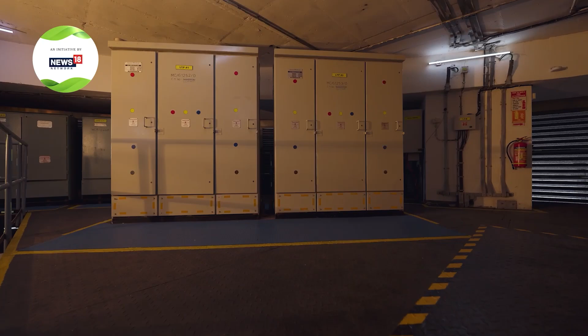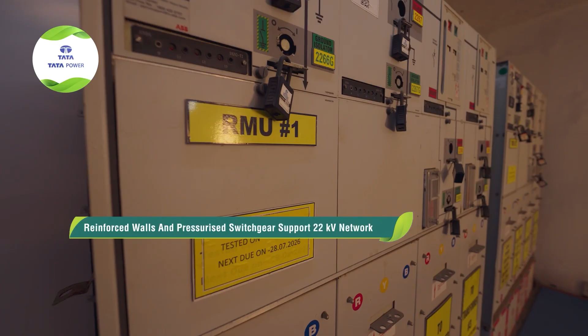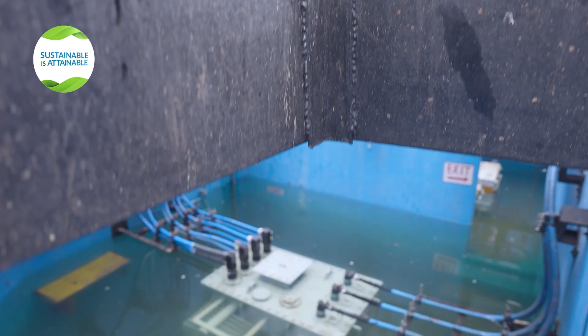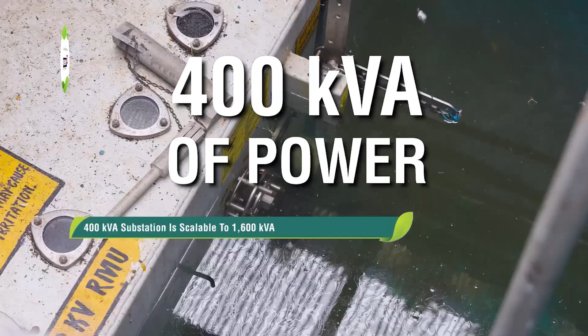In South Mumbai, space is scarce; every square meter is a fight. That's why one of India's first 400 kVA underground substations was built directly beneath this commercial hub. Here, 22 kilovolts of electricity flow silently behind reinforced walls and pressurized switchgear, hidden directly beneath the city streets, out of sight, out of space, but powering everyday life. Today it transmits 400 kVA of power with capacity to scale to 1600 kVA in the future, enough to serve 500 mid-income households. Here we try to identify a solution wherein the leakage issue during rain can be solved and the space can be optimized for the electrical substation.